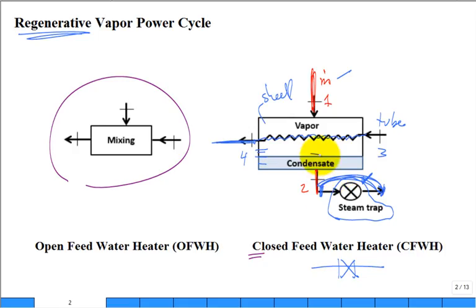It basically forces only liquid to go through. Once you understand what they are, you understand how to go out into an actual power plant or other facility where they have steam and diagnose it. You'll find that there's actually a lot of broken steam traps out there in practice. Not at the good facilities where they have good engineers, but at other facilities where they just don't pay their engineers or maintenance people. There's a lot of broken steam traps out there letting vapor through when it shouldn't. So if you get out there and have problems at a facility, a lot of times as an engineer you're asked to go diagnose and find the problem and fix it, right?